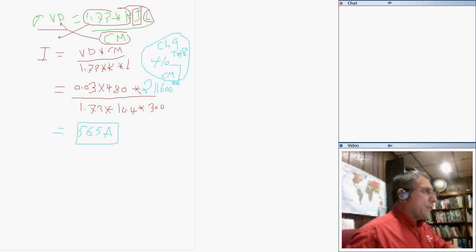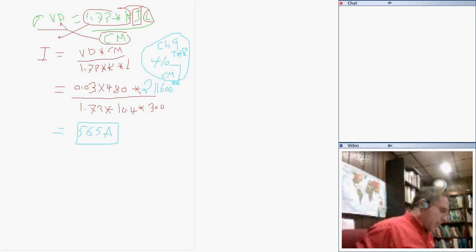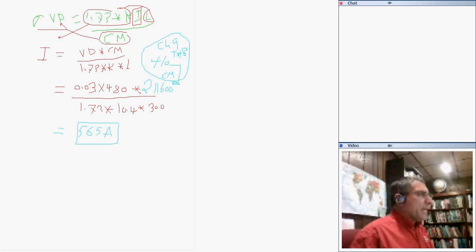So what we're doing here. Okay, let's see if it doesn't make sense. The number is too high. Okay, 1.73, no. kcmil over CM, okay. We need current, so CM times voltage drop divided by 1.73 K L. Okay, anyone with something different, guys? Can you chat with me? Do you have your handy? So that's the number that we came up with.